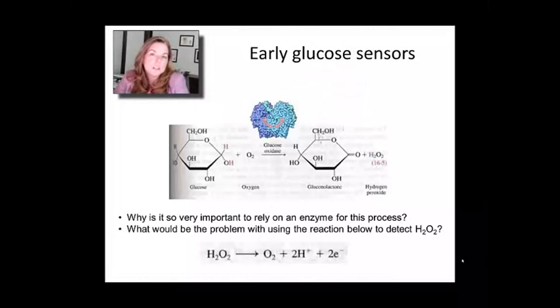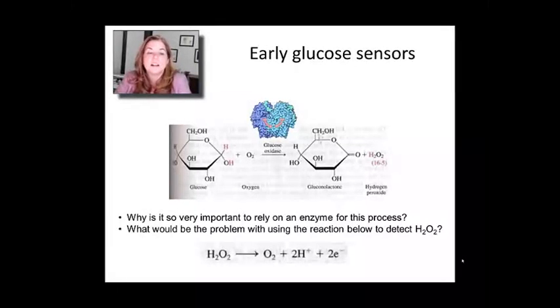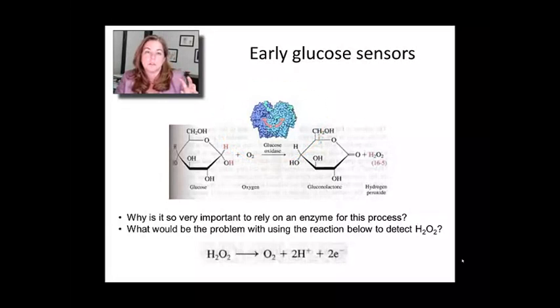Early glucose sensors realized that measuring glucose in blood creates a specificity problem—you've got many types of sugars in blood. If you're interested in glucose, you need specificity, and one of the best places to get that is nature herself. Glucose oxidase is an enzyme that converts glucose to gluconolactone, very specific just for glucose.